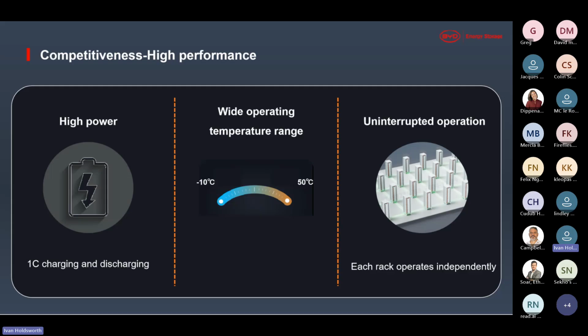It's a 1C battery, so you can charge and discharge at 1C. And it does have redundancy. So if one of those towers goes out, the other towers keep working. And there's also an AC connection on your master tower, so that if your master battery has an issue, the PDU that communicates to the inverter can still be powered to keep your whole battery bank alive.